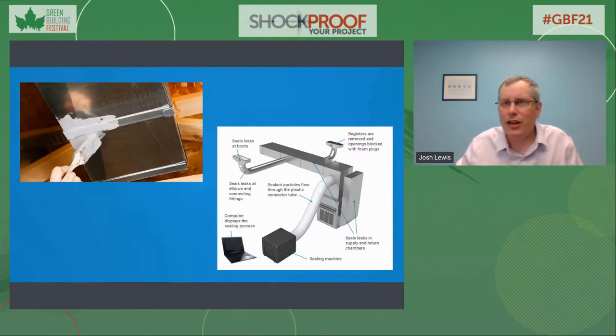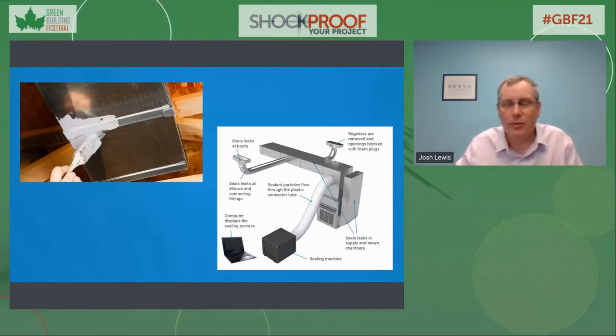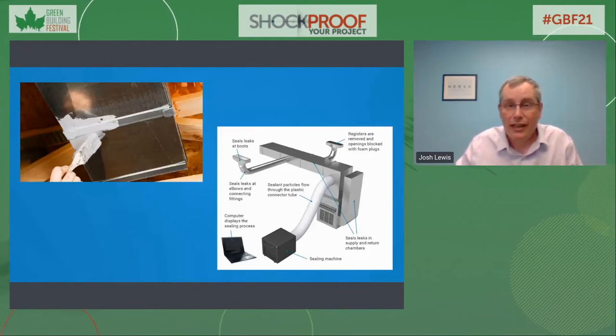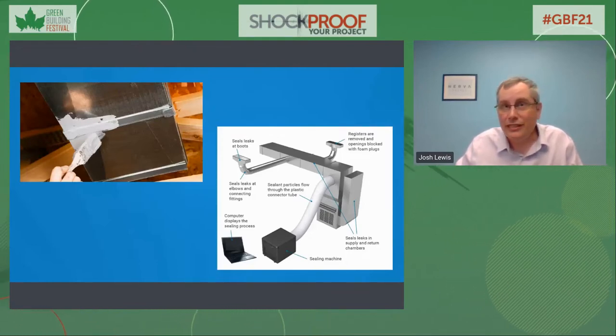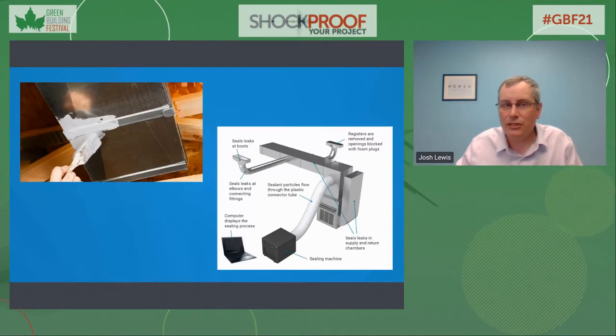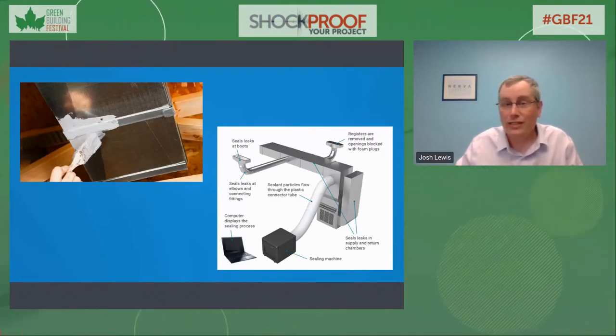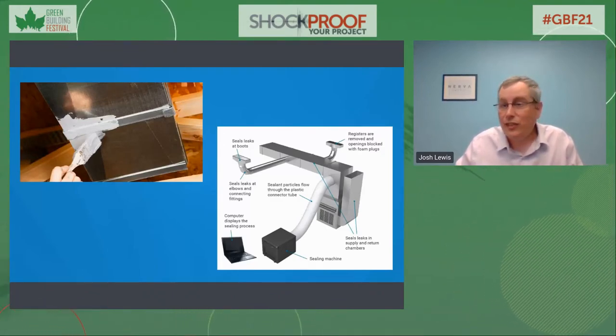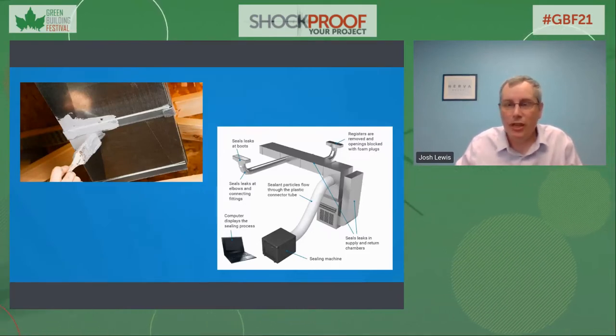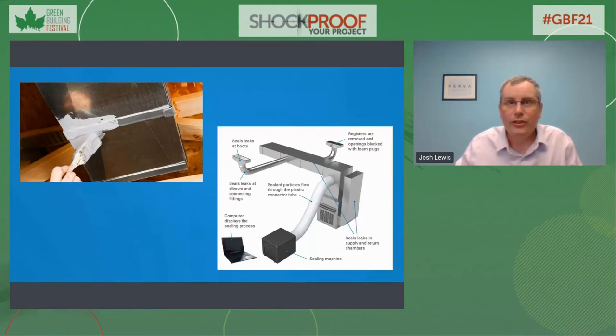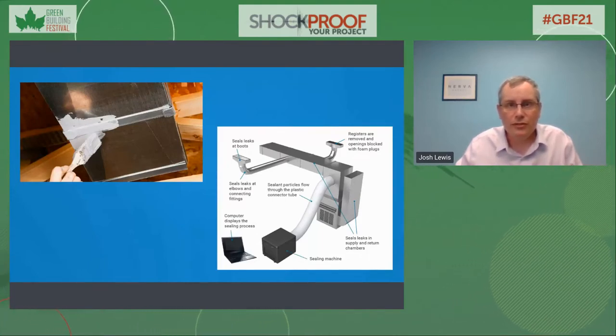Any air leaking from ductwork before it reaches the occupied areas of the building reduces air circulation rates and wastes energy, as the areas it is leaking into, including ceilings, shafts, and mechanical spaces, are not designed for nor intended to be ventilated. If duct leakage is reduced, there will be immediately more air circulation in the space that people occupy, improving indoor air quality and reducing the risk of disease transmission.